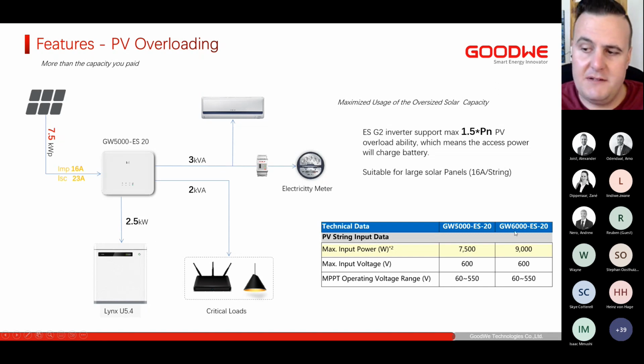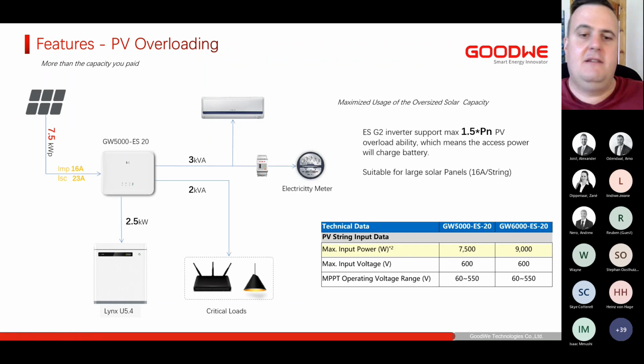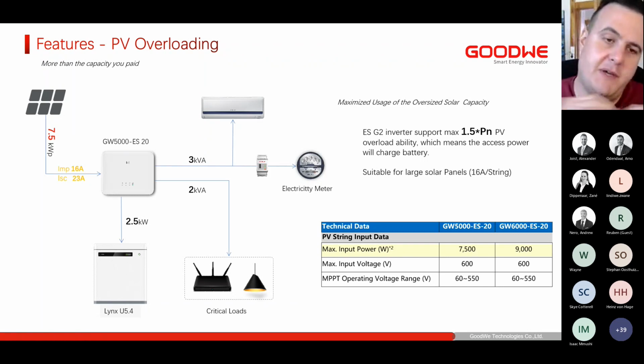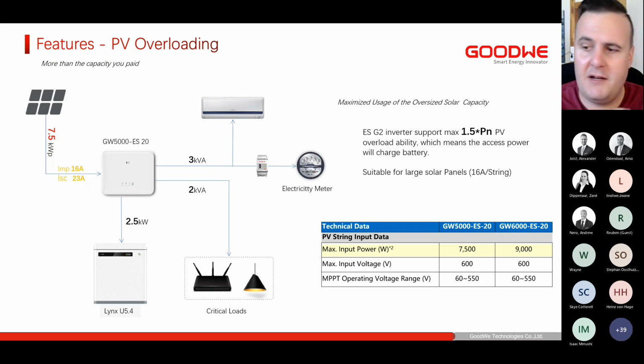The same goes for the ES 6 kilowatt. You'll see they can take 9 kilowatts of DC. So especially if a customer has higher energy requirements, so a much higher base load, but their peak demand does not, or hardly ever, exceeds the inverter's rating. A lot of customers might only peak over that 6 kilowatt once or twice or 3 times a day for a short period of time. Then the 6 kilowatt is more than sufficient for those customers. But that higher base load will require more PV to compensate the consumption as well as charge the battery bank. So this gives us that flexibility to do more with the system.